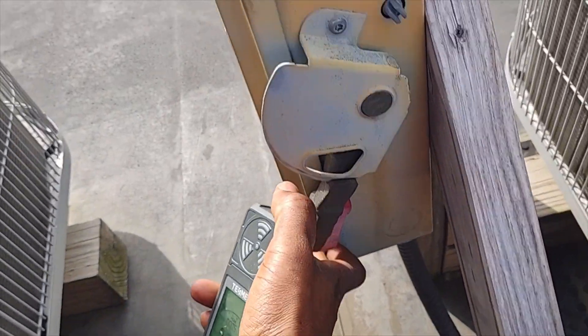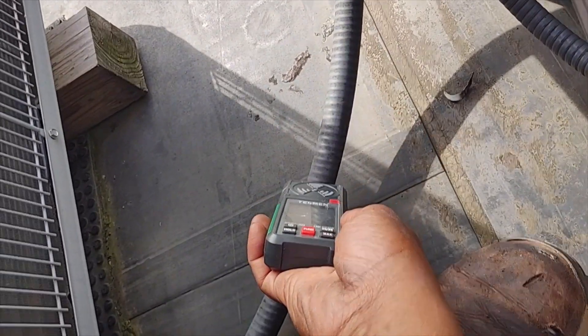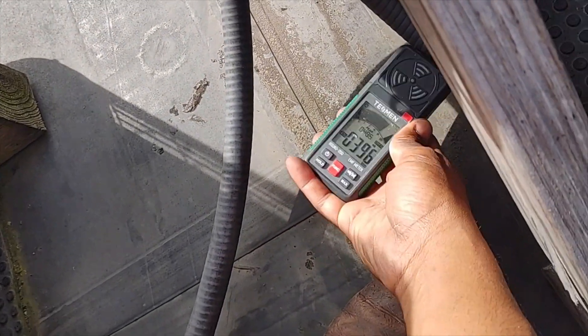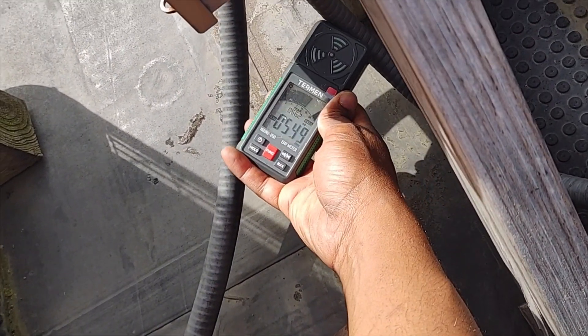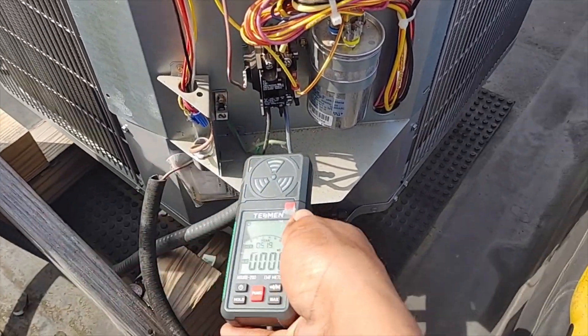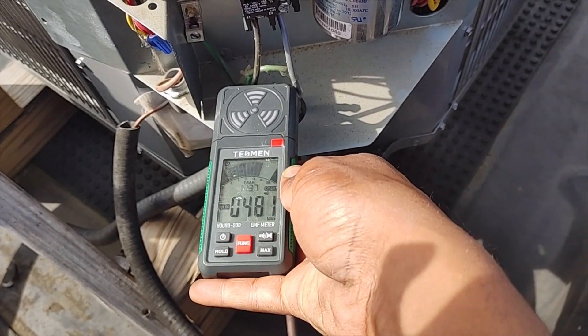Let's go ahead and put the high voltage on and see what we get. I also want to test — oh nice, I can read through the conduit, which is cool. I'm going to hit this and turn that on. I always want one where I can read through the conduit; if it's not strong enough to read through conduit I don't want to mess with it. Yeah, that's a nice strong signal there.